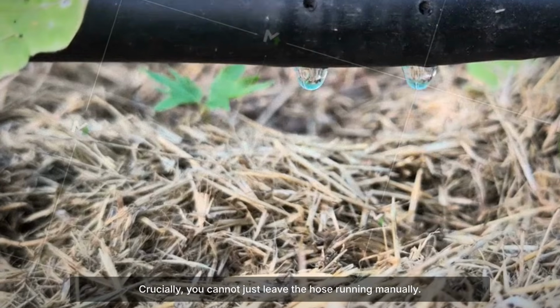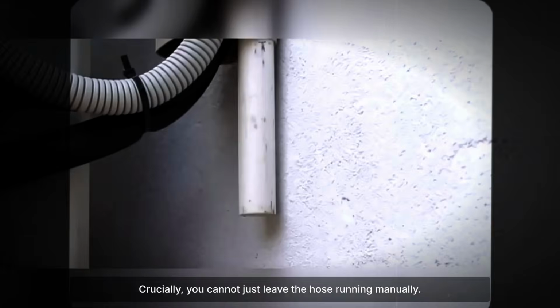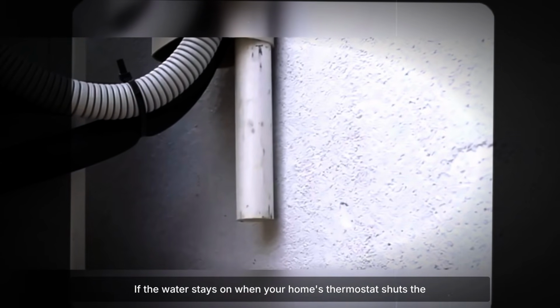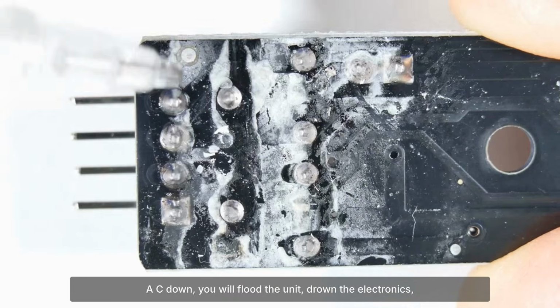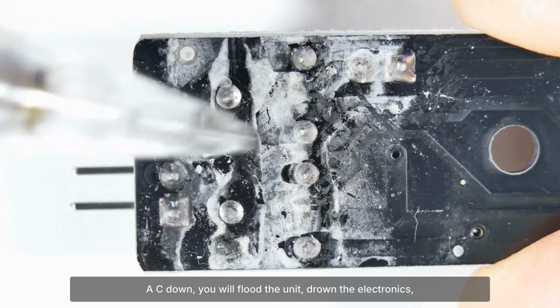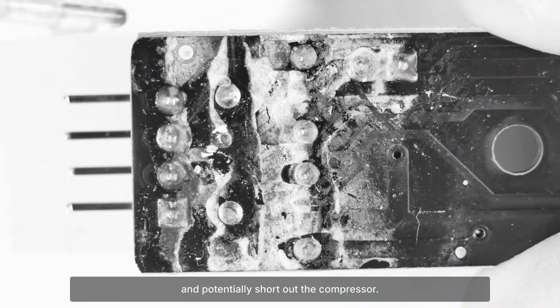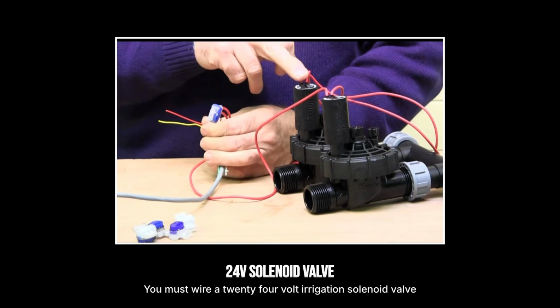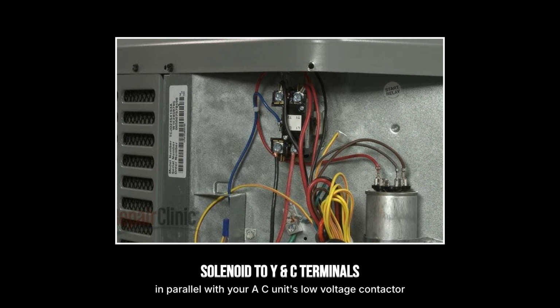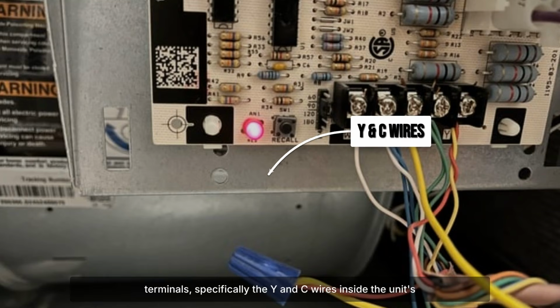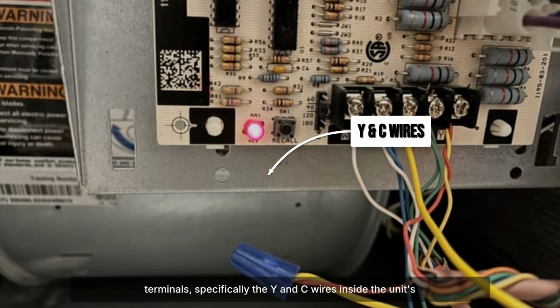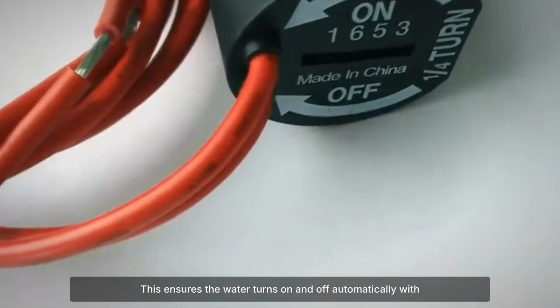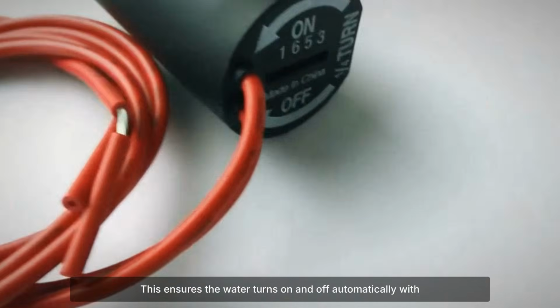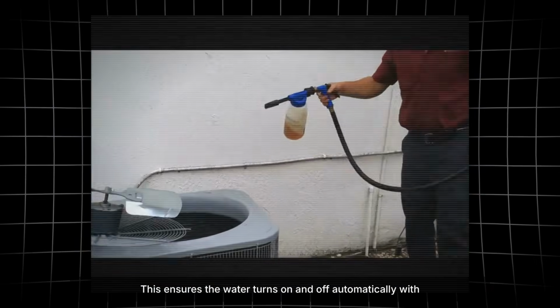Crucially, you cannot just leave the hose running manually. If the water stays on when your home's thermostat shuts the AC down, you will flood the unit, drown the electronics, and potentially short out the compressor. You must wire a 24-volt irrigation solenoid valve in parallel with your AC unit's low-voltage contactor terminals, specifically the Y and C wires inside the unit's control panel. This ensures the water turns on and off automatically with the compressor.